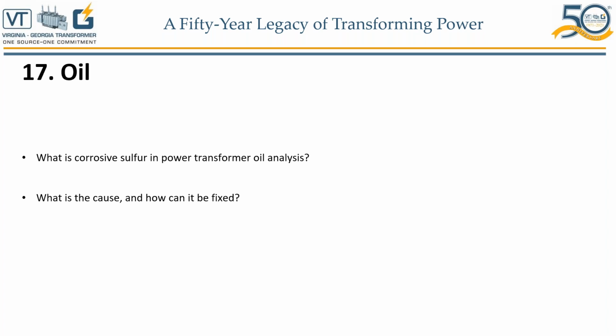Oil suppliers, during the refining process, try to remove many of these corrosive sulfur species to make more stable compounds. But they may not always be successful, and they may not be able to remove all these sulfur species from the oil. Mineral oil comes from the earth, so when they take it, it already has sulfur, and they try to remove it. They may not be successful 100% of the time, and some small quantities may be left behind. So that's where it's coming from. Corrosive and reactive sulfur compounds can react on contact with copper and other metals. Copper and silver are the least resistant to sulfur, and what it does is form copper sulfide.